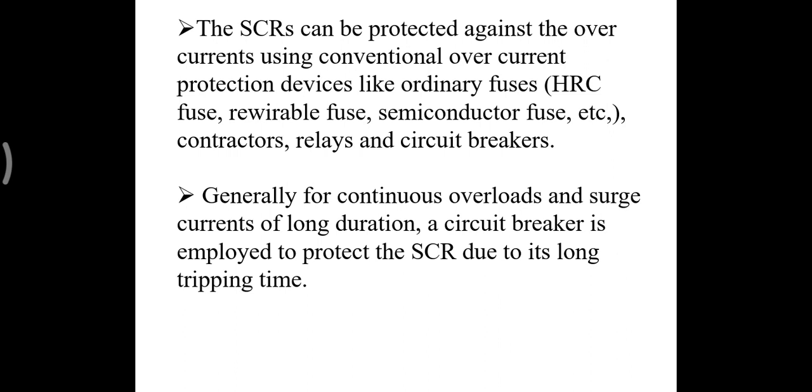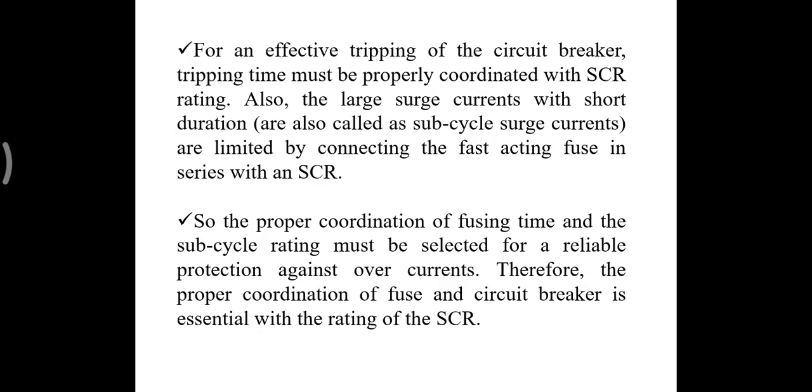For continuous overload and surge currents of long duration, a circuit breaker is employed for the protection of the SCR. That means if continuous overloads occur, in that situation we are using the circuit breakers. For effective tripping of the circuit breaker, the tripping time must be properly coordinated with the SCR rating. Large surge currents with short duration are limited by connecting a fast acting fuse in series with the SCR.